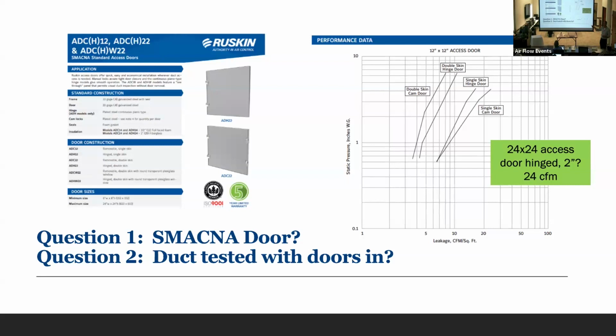Here's SMACNA rated Ruskin, that's a good brand, it's SMACNA rated. It's a 2x2 access door. How much does the hinge door leak? Well, we talked about maybe $5 a CFM, right? On the low end. So two inch pressure, 2x2 door. So where's our pressure? Our pressure is here, 2 inches. We go across this double skin hinged access door. This is for a 12x12, it leaks like 8 CFM, 7 CFM, so times 4. So 24 CFM times $5. It's $100 a year just out of that access door.